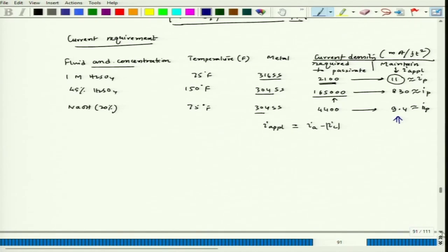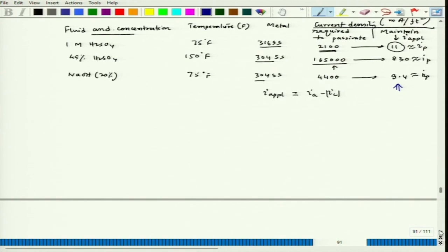That means we know what my corrosion rate would be when it has reached the protection point. Now, we can talk about some differences between cathodic and anodic polarization, and differences between the two modes of protection in case of cathodic protection: ICCP and sacrificial anode. If we look at those differences, we can pinpoint some of them, from the design aspects. One difference is that in one case we need an external power source, in another case we need no external power source, but there are some other differences. So, let us talk about that. Differences between ICCP and sacrificial anode.